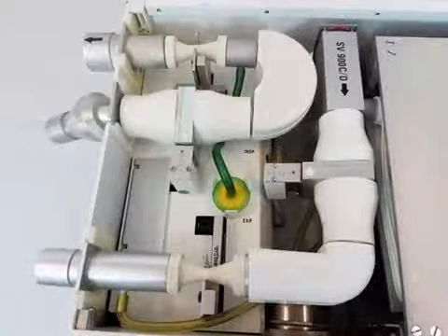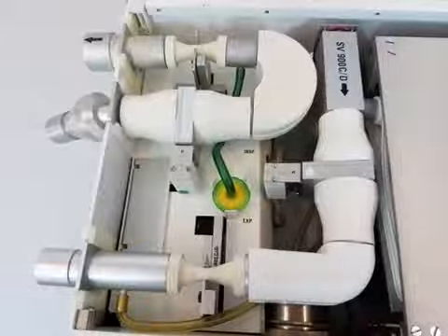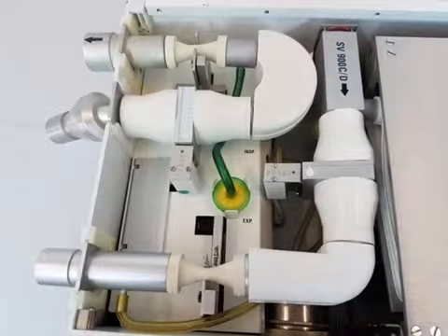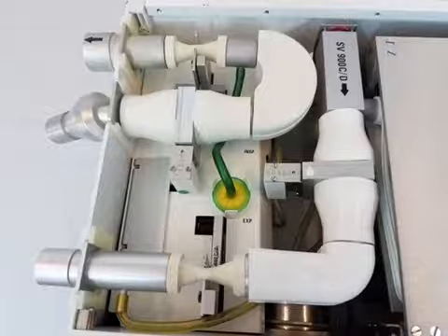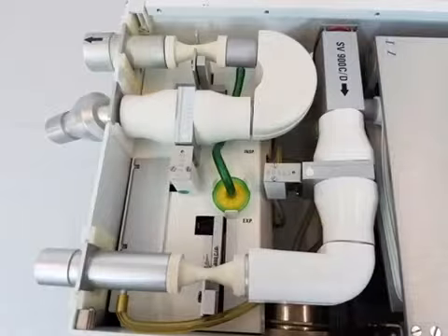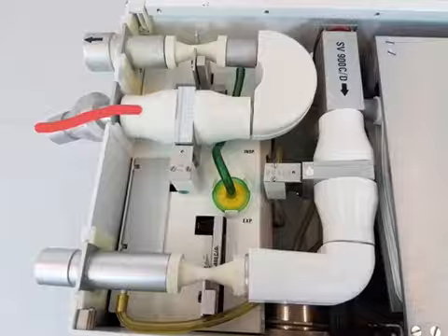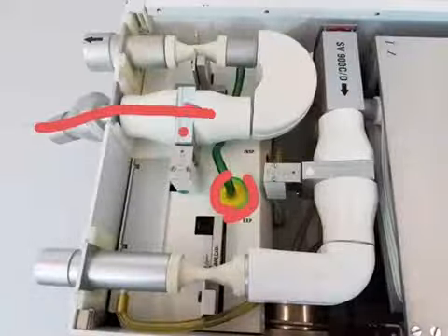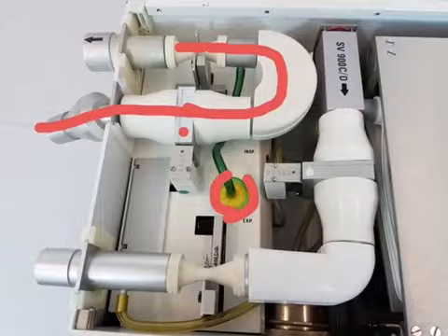And then lastly, gas is exhaled through here, and there's a little flap valve in there. It prevents a backflow of exhaled gases, and it's also necessary for the triggering function of the ventilator itself. To review, the gas from the patient comes inside the ventilator. It goes through my expiratory flow transducer. It's measured by my expiratory pressure transducer. So flow, pressure, goes through the loop. Here's my expiration valve, or expiratory valve, which regulates my PEEP also, then it goes out of the ventilator through the flap valve. And that's all.